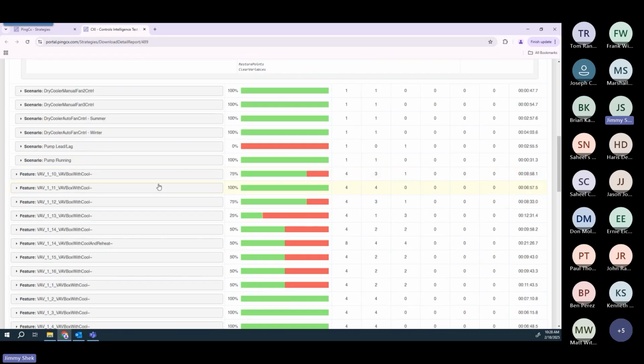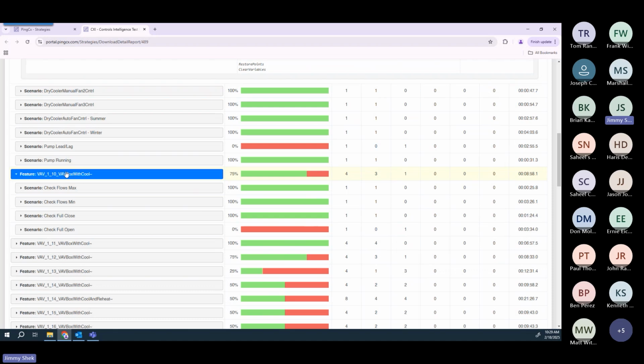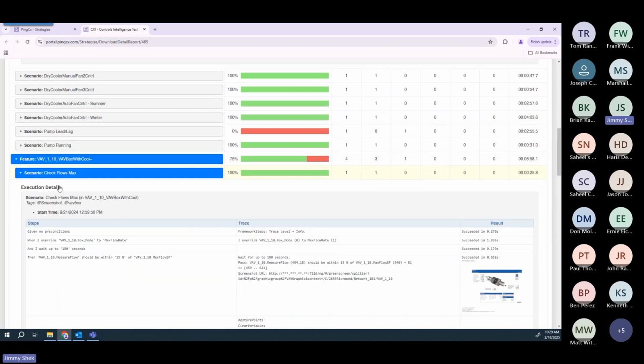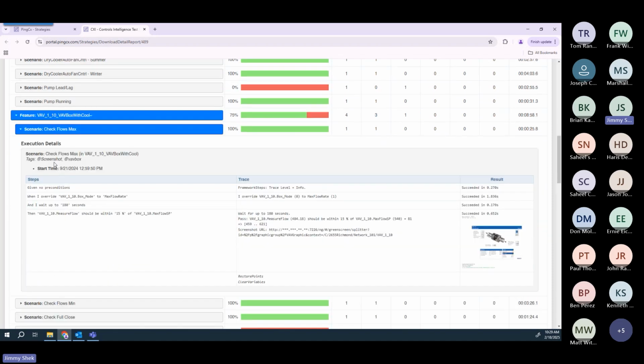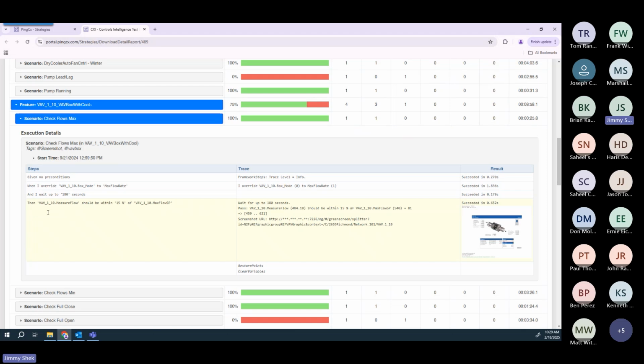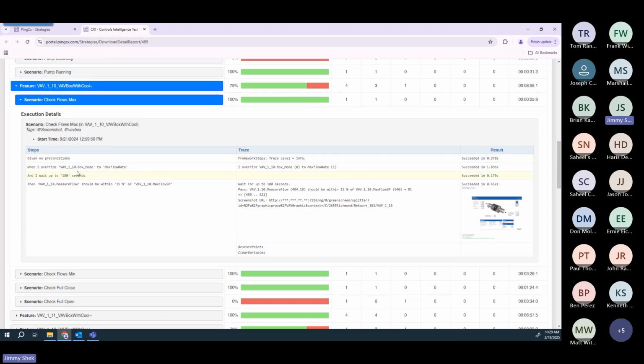Okay, so the next example I want to just quickly show is related to VAV boxes, right? So in this case, we have VAV 1-10, and the scenario is called check flow max, right? So the steps here are given no preconditions. When I override the 1-10 box mode to the max flow rate, wait up to 180 seconds, then the measured flow should be within 15% of the max flow set point.